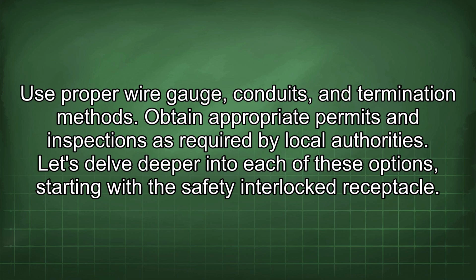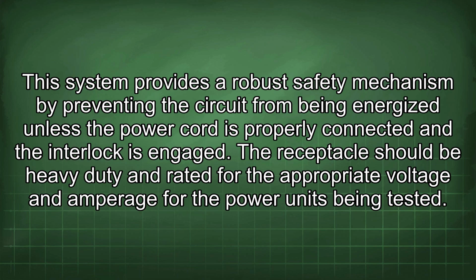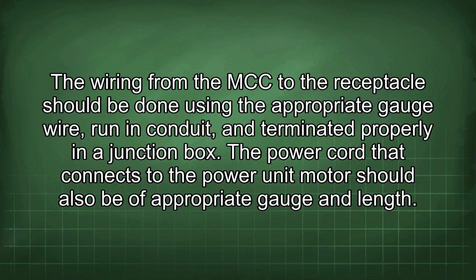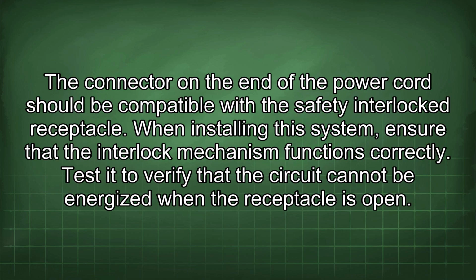Let's delve deeper into each of these options, starting with the safety interlocked receptacle. This system provides a robust safety mechanism by preventing the circuit from being energized unless the power cord is properly connected and the interlock is engaged. The receptacle should be heavy-duty and rated for the appropriate voltage and amperage for the power units being tested. The wiring from the MCC to the receptacle should be done using the appropriate gauge wire, run in conduit, and terminated properly in a junction box. The power cord that connects to the power unit motor should also be of appropriate gauge and length. The connector on the end of the power cord should be compatible with the safety interlocked receptacle.